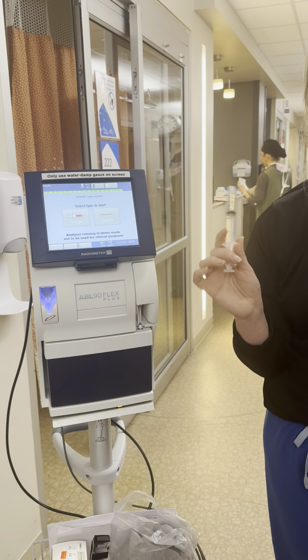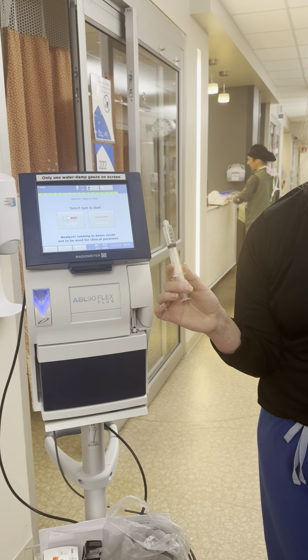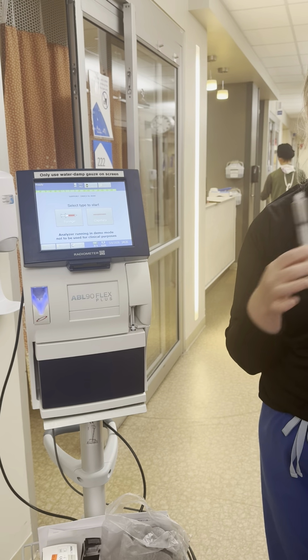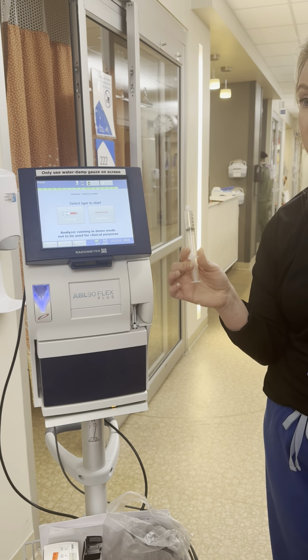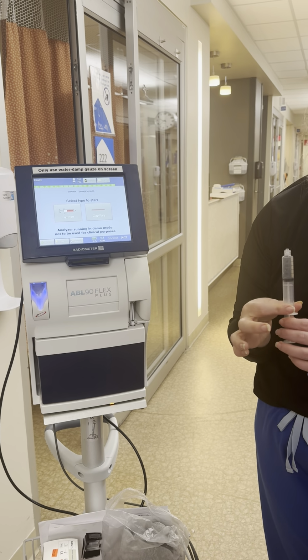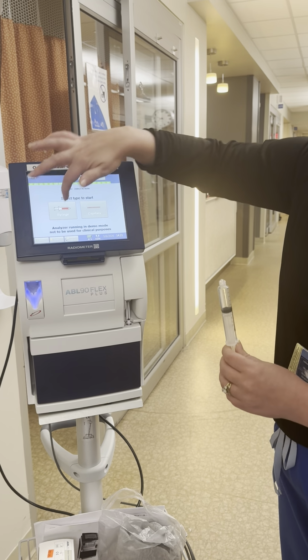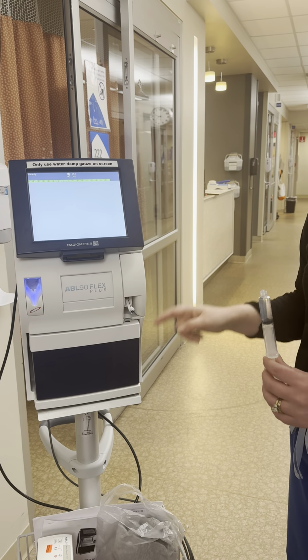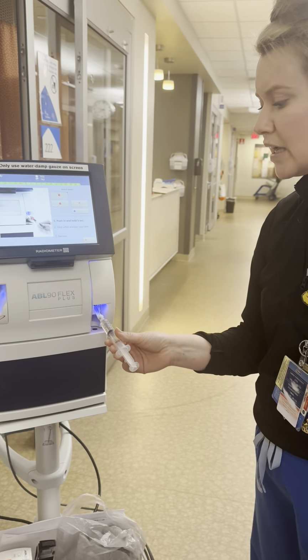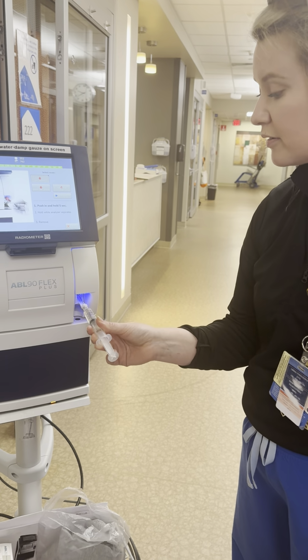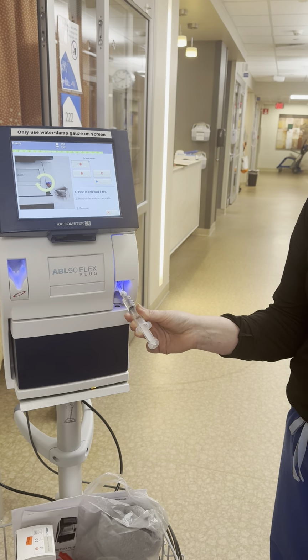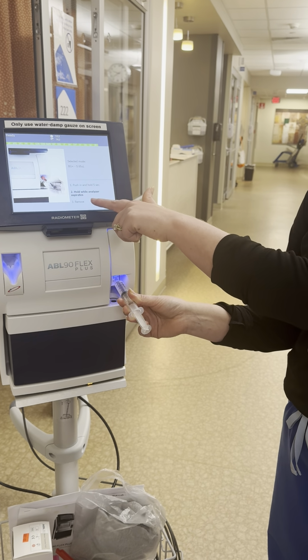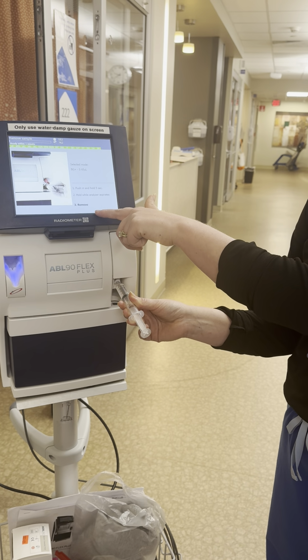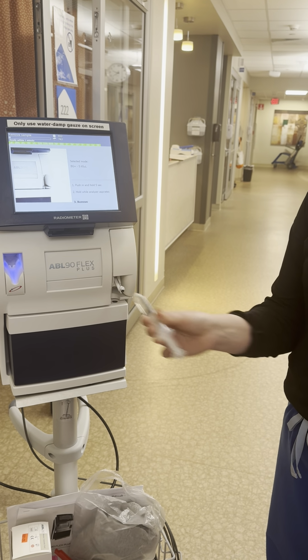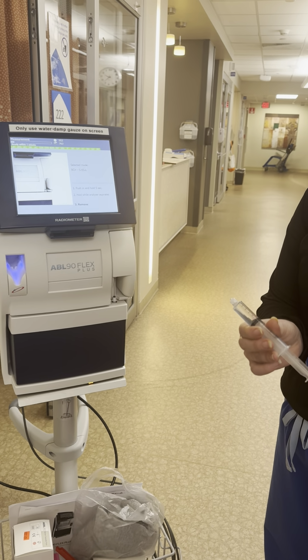Make sure you have your sample in hand before you come to the machine. It's going to time out after 20 seconds. So just already have it, bring it to the machine, and it's really fast. Your sample's going to run in 10 seconds. So you hit syringe mode, and the probe pops out. It doesn't screw in, there's no luer lock, but you can feel the divot where it fits right into that groove. And then you push in, and it'll prompt you on the screen. It'll tell you when to remove, and it beeps. And then you'll pull out.